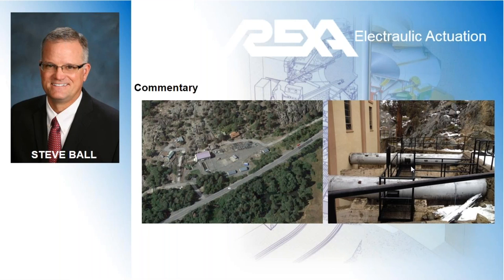We started out understanding that the penstock system was, of course, aged. It had been there from the original construction of the plant. So we had an analysis and modeling done to determine what we would know as forces, and what the acceptable limits of needle closure and needle opening would be, and what would be a reasonable tolerance for pressure rise and pressure drop. In other words, still thinking of water hammer, as well as any kind of pressure rise from rapid needle movement. In that analysis, it was determined that plus or minus 10% was a reasonable area to look at.